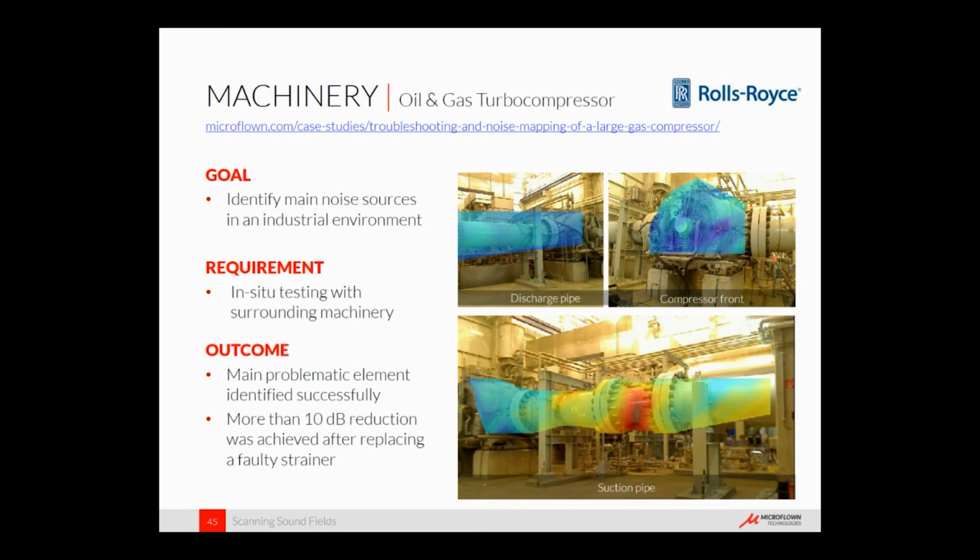So one company was responsible for the gas compressor, that was Rolls-Royce. Another company was responsible for the piping infrastructure. And in this case, when you entered this facility, you directly wanted to go out. It was an insane noise level, and the peak measured was like 115 dB.